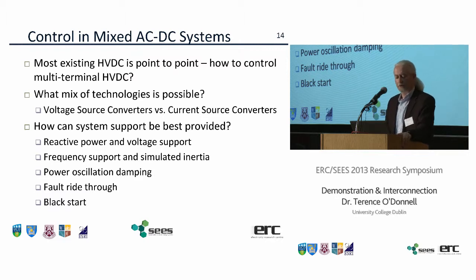This brings a lot of issues around how you control such a system. In particular, most existing HVDC is point-to-point, but it's envisaged that any future system would be a mesh, multi-terminal system. There isn't much experience with controlling and operating multi-terminal HVDC systems. There's also the question of different HVDC technologies: classic HVDC based on thyristors, and the more modern voltage source converter technology based on IGBTs. Any system would practically have to consist of a mix of those because of the large installed base, raising questions about how you control it with such a mix.